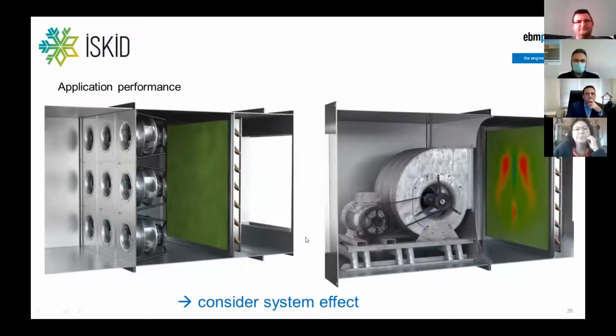In the application, this is another distribution effect when you use a blower. So a blower tends also to have a quite big air velocity in the outlet area, especially on the upper part of the discharge flange. And this you can see also when the air meets the coil. On the other side, when you have a plenum fan, or even a fan grid, fan wall, the air distribution over additional components in the unit is better, more beneficial.